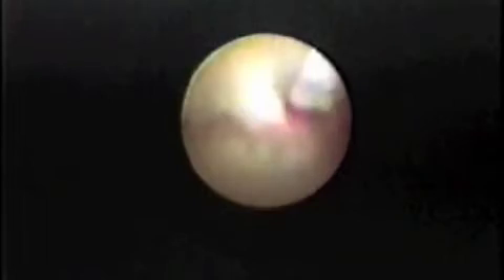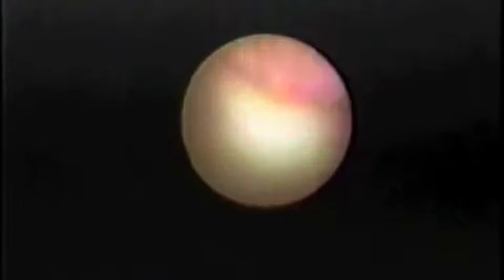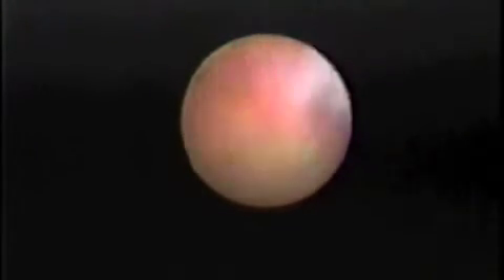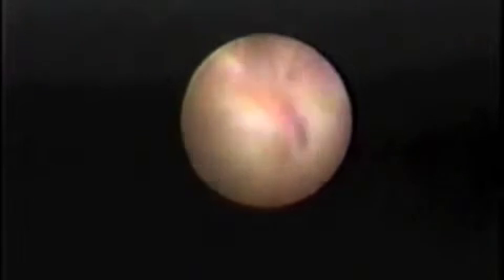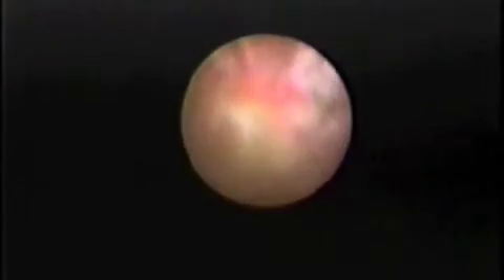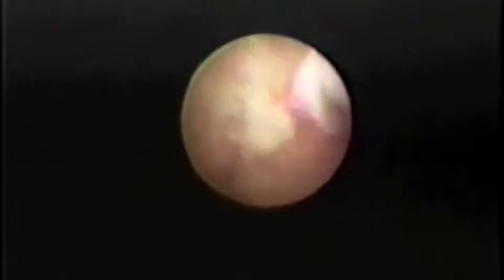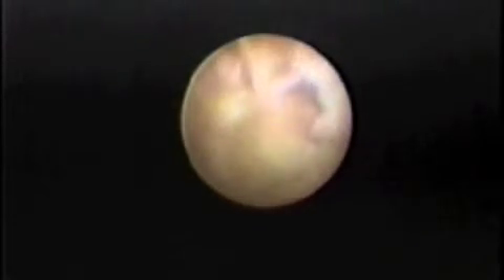The Holmium-YAG laser light only travels a short distance in water. That's why this laser is so good for discectomy. Almost all the light is absorbed completely within 2 millimeters. While this short range adds to laser safety, it does present a difficulty. The laser fiber tip needs to be in contact or near contact with the disc for it to ablate. If you're firing and nothing seems to be happening, consider advancing the laser fiber.